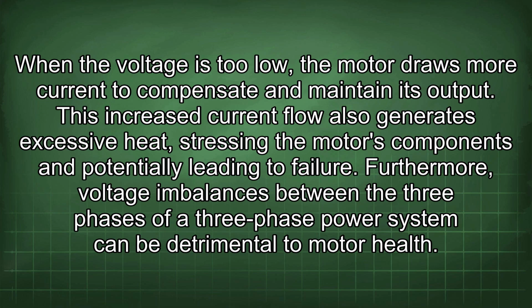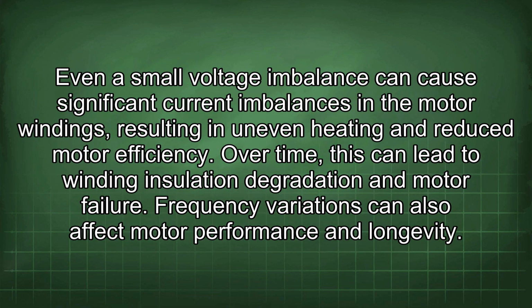Furthermore, voltage imbalances between the three phases of a three-phase power system can be detrimental to motor health. Even a small voltage imbalance can cause significant current imbalances in the motor windings, resulting in uneven heating and reduced motor efficiency. Over time, this can lead to winding insulation degradation and motor failure.